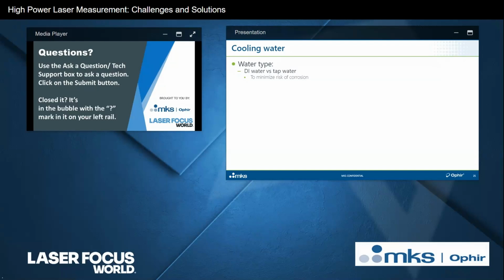When the pH of the water becomes slightly acidic, that's when you start getting into trouble, because then ions get leached out of the different metals that the water comes into contact with along its path, and then you can start having problems. Tap water can sometimes work also. It really depends on what's in the water in your particular region. In our specifications, we always list the recommended and the maximum and the minimum flow rate of the water, and the temperature range of the water, and the pressure drop across the water tubes in that cooling system. These are all things that are listed there.